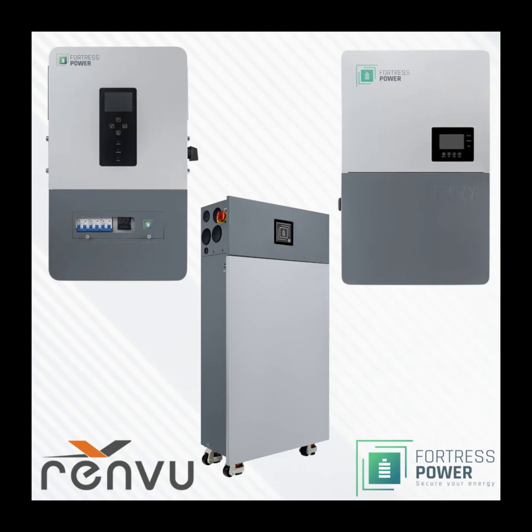E-Way on top that allows for the 750 amp bus bar as well as the Guardian to be mounted inside of it. This one again can be scaled up to 256 kilowatt hours, so that would be a total of 16 eBoosts in parallel for one singular application. So a wide range, can go as small as 16 kilowatts and as large as 256.